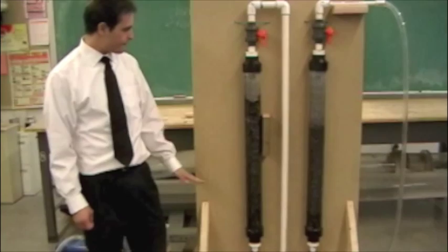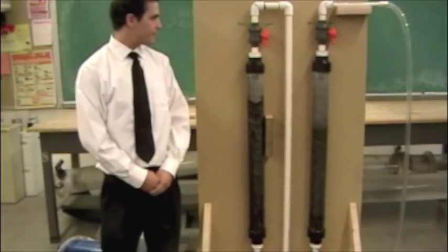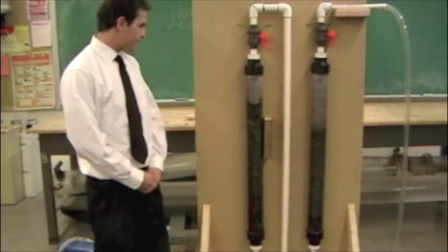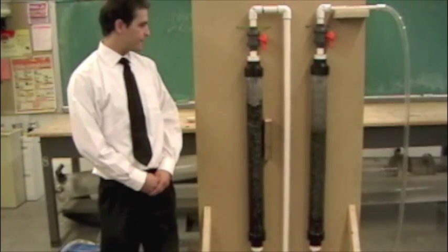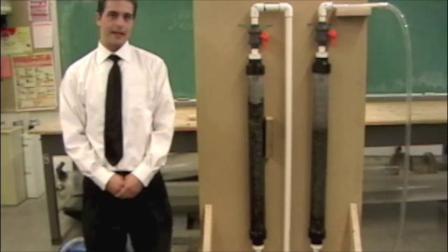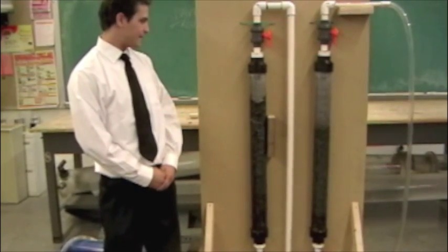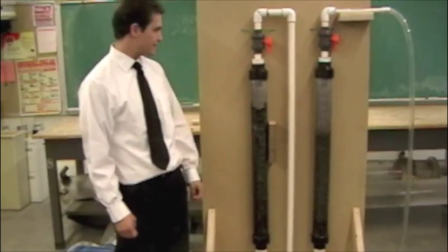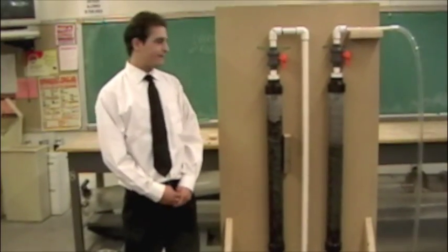It also is an upflow system. Many systems run downwards to take advantage of gravity, but we thought that an upflow pressure system would be a better fit for our design. Upflow allows for even flow up through the column, where there will be less channeling throughout the system, as there could be in gravity flow. It allows for an increased contact time over downflow.